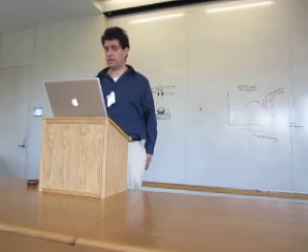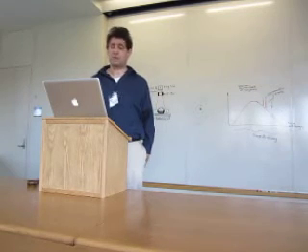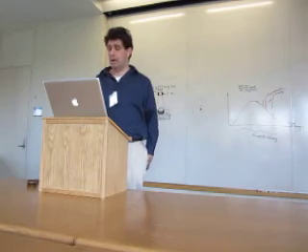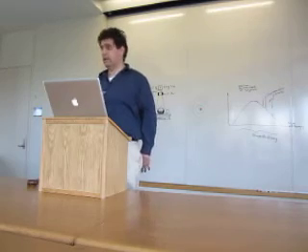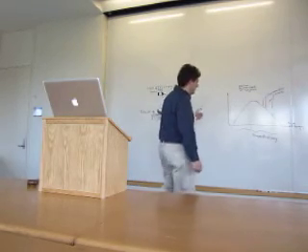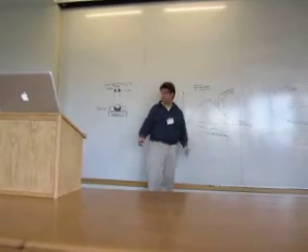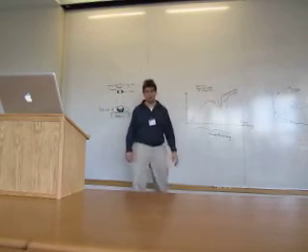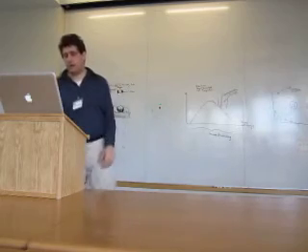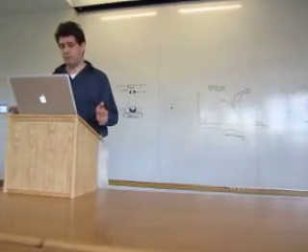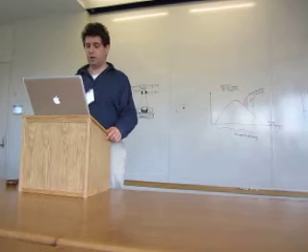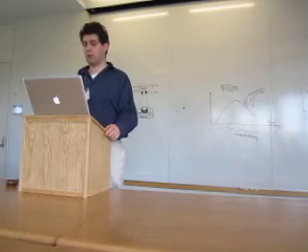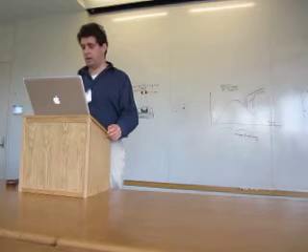The second kind is an ejection of an inner orbital electron, so that is an ionization. And that produces characteristic X-rays. If we look at the spectrum of energies coming in the X-ray beam from this tungsten target, we get these little spikes, which are the characteristic X-rays. And finally, you have a broad band of X-ray energies resulting from something called Bremsstrahlung, which is German for braking radiation.